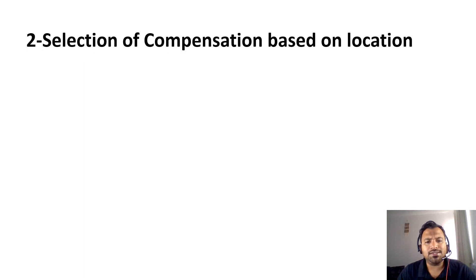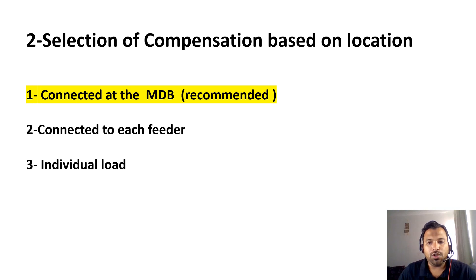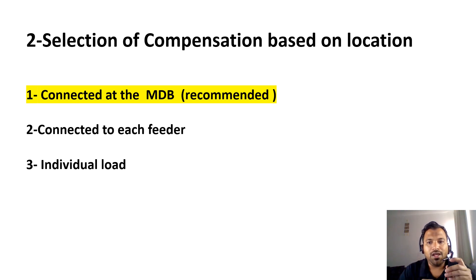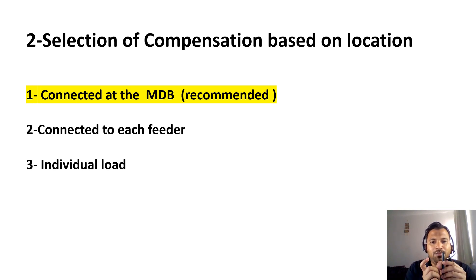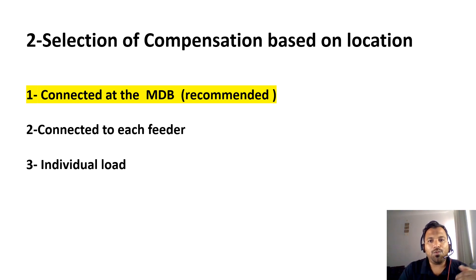Step 2 is compensation based on location — where we want to place the capacitor banks. There are three options: connect it at the main DB side, connect it to each feeder, or connect it to individual loads. When studying theory, we learn that capacitor banks should be placed near the equipment — for example, fans have built-in capacitors, and motors have capacitor banks installed with them to compensate the inductive load.